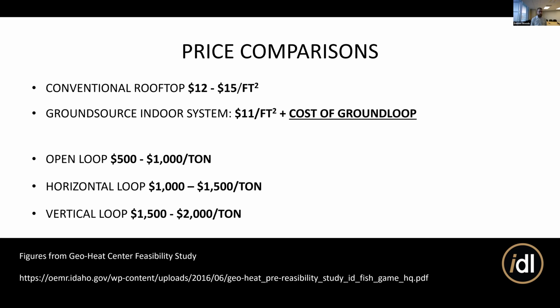They found that a conventional rooftop system for this building was going to be about $12 to $15 per square foot. The ground source indoor system, so these are the indoor coils, ductwork, distributing system, was going to be less than that, $11 per square foot. But you have to add on to that the cost of that extra ground loop. And that ground loop cost is going to vary not by square footage of the building, but by tons of capacity. So an open loop, they were looking at between $500 and $1,000 per ton.